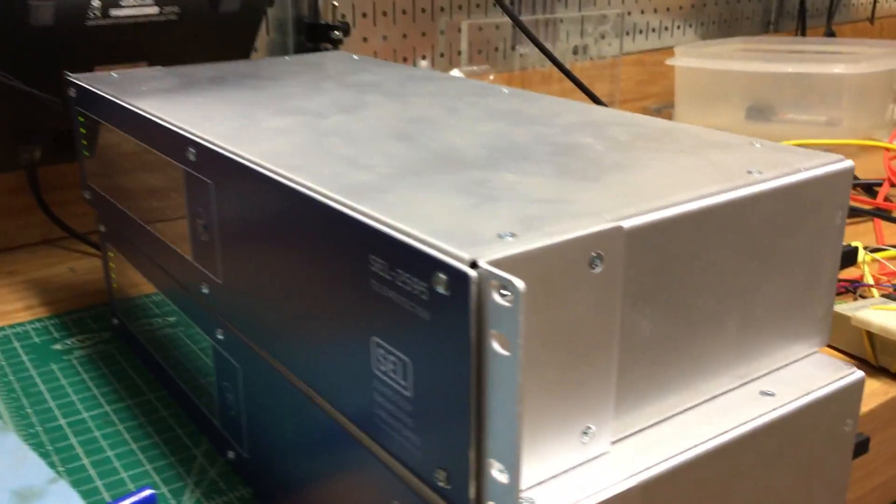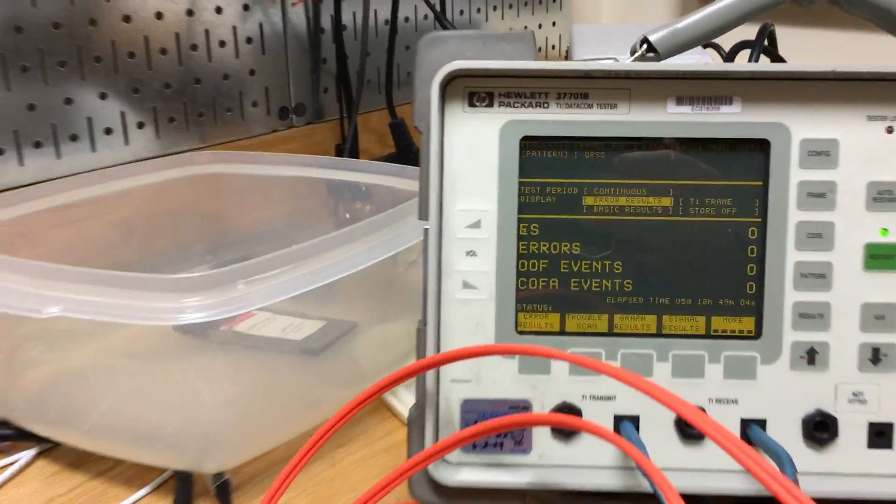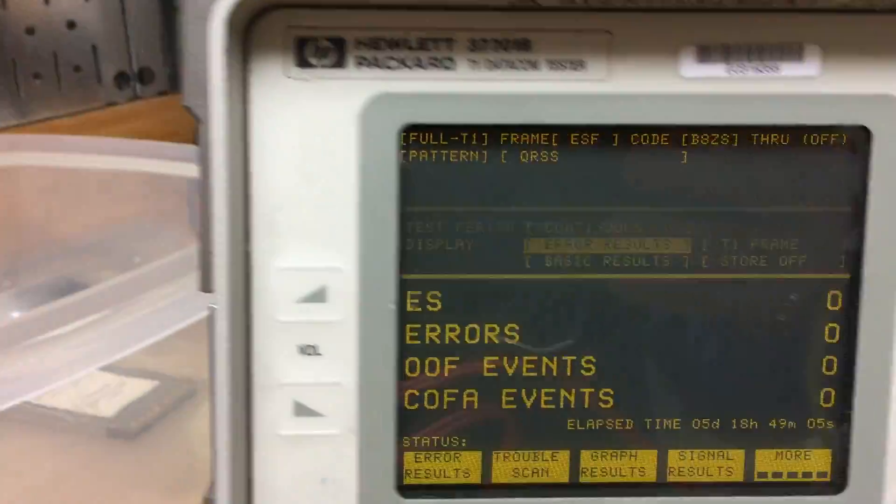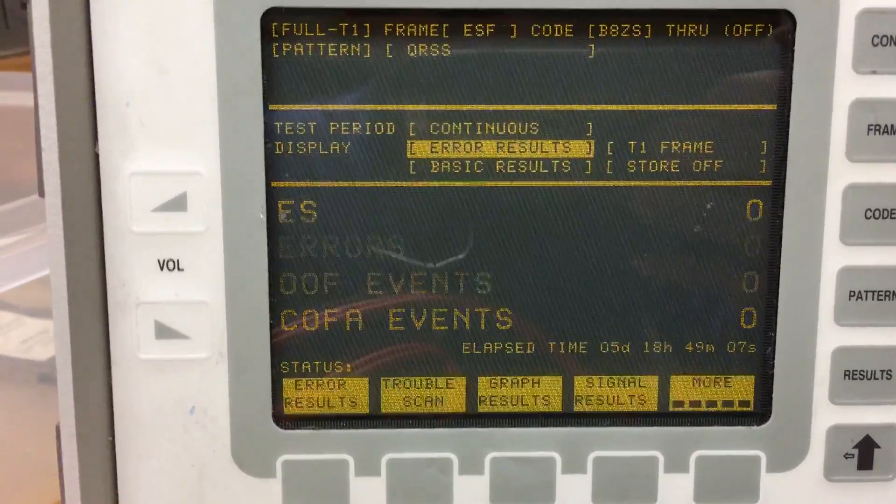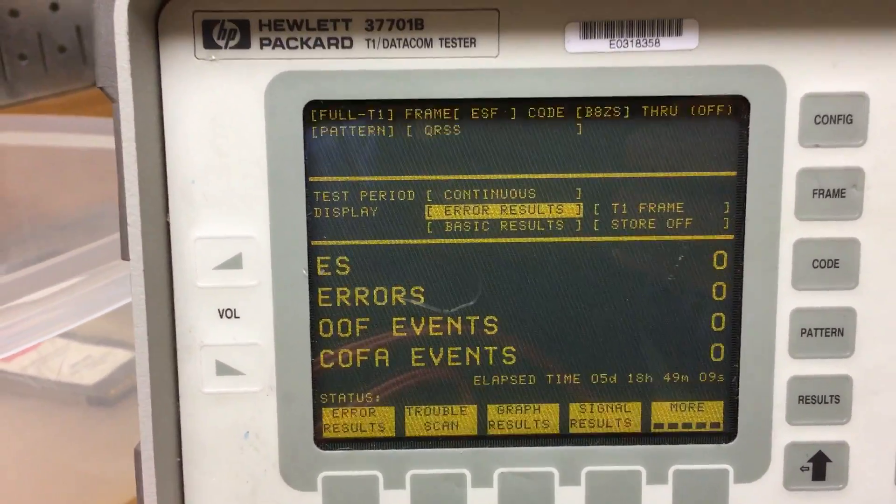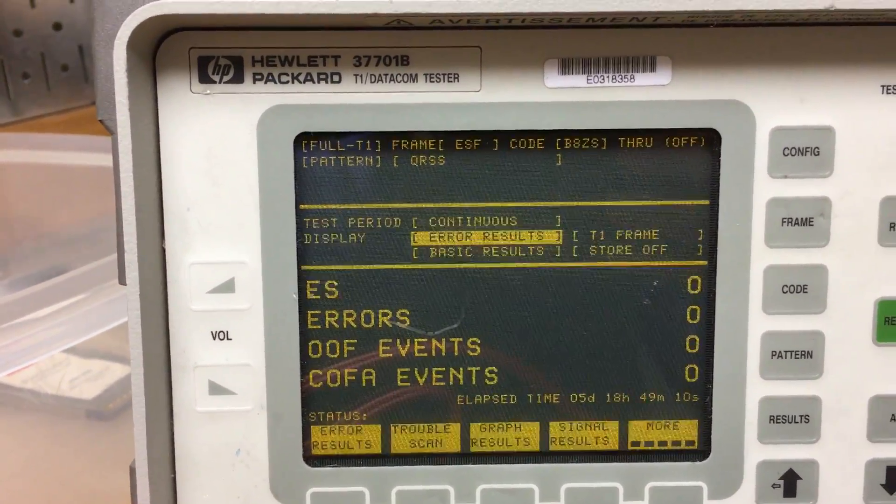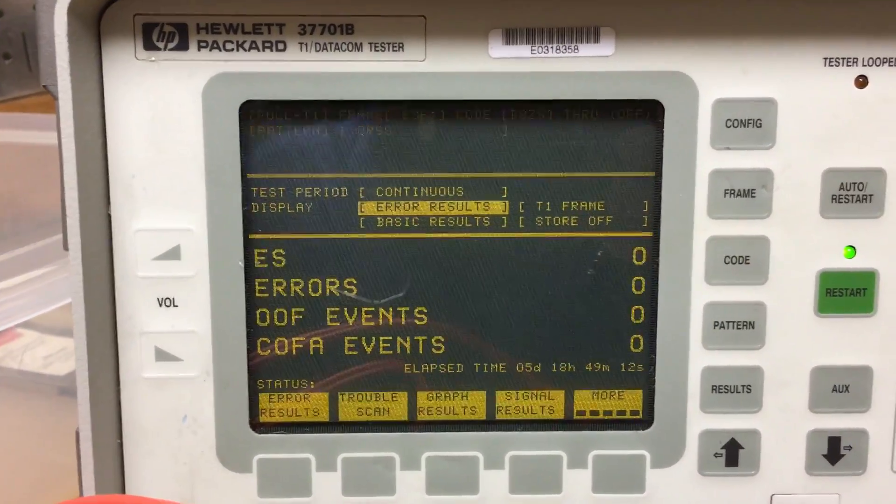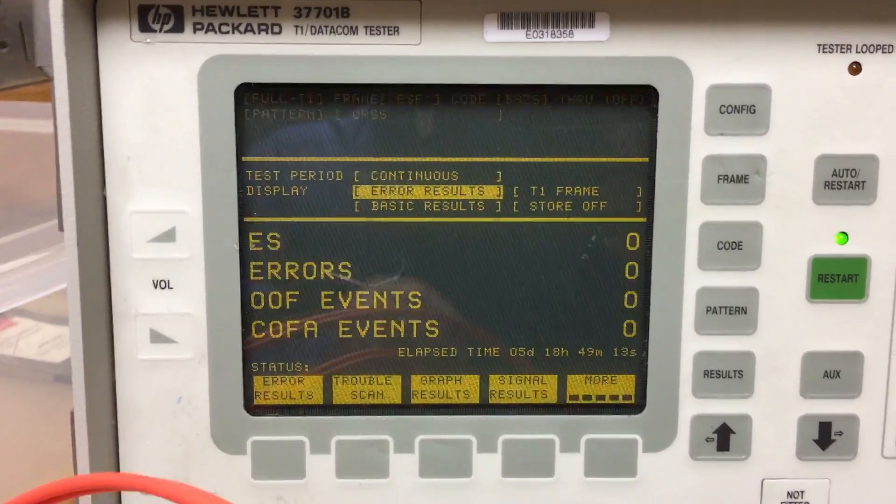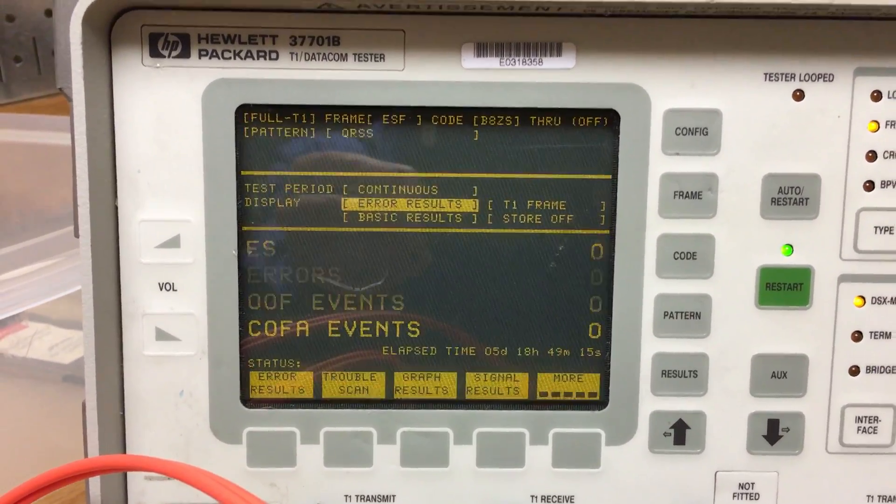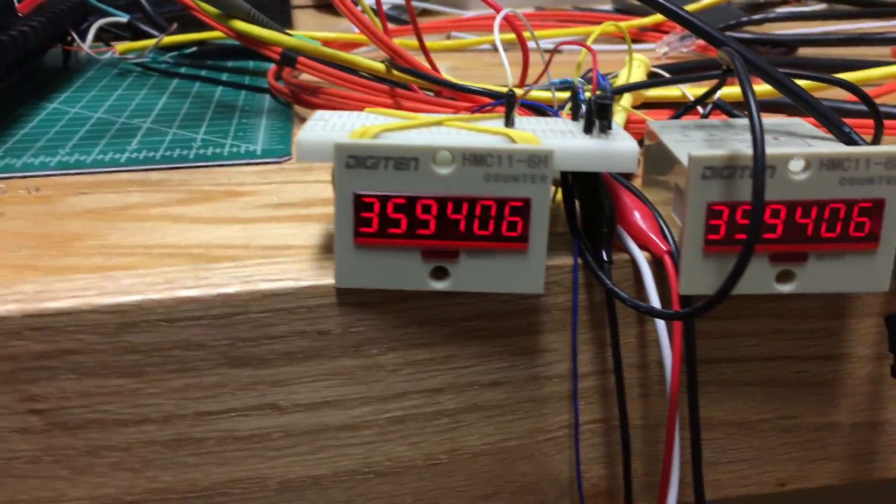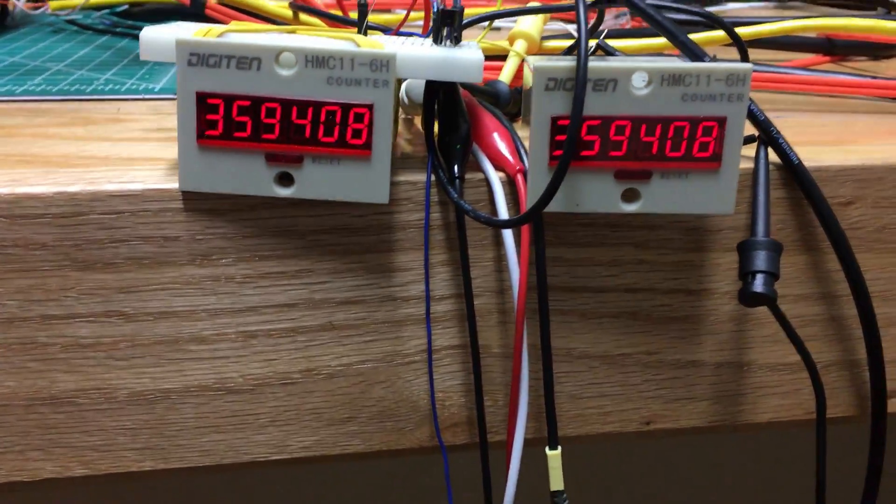But this has been going on for now, let's look down there, five days 18 hours, nearly six days. As you can see the T1 tester shows zero errors, so for six days the transfer trips are up to 359,000 trips that were sent on the left.